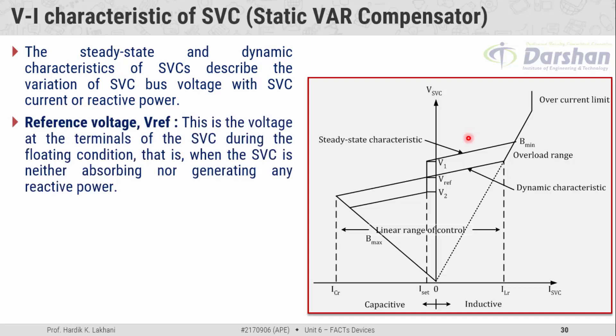The first point in the VI characteristic is the reference voltage, denoted by V_reference. This is the voltage at the terminals of the SVC during the floating condition, meaning the static volt ampere reactive compensator is neither absorbing nor generating any reactive power. When the SVC is connected to the line, V_reference is the rated voltage of the line at the point of connection, and it is also considered as the voltage across SVC when it does not absorb or inject any reactive power into the system.